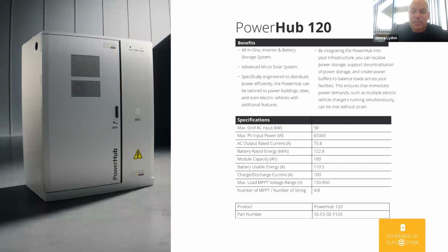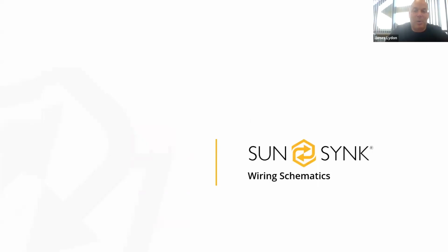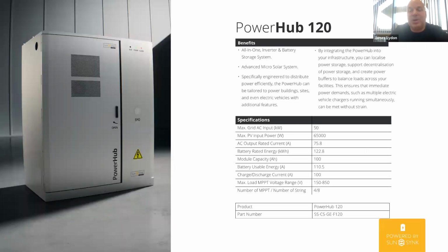The power hub, so this is obviously an outdoor unit, and this essentially has the high voltage kit built in as standard. So inside the power hub, you've got a 50 kilowatt hybrid inverter and two of our 61.4 kilowatt hour stacks. So just over 120 kilowatt hours of storage. And the power hubs are great because they're all pre-wired. You don't need to do anything. They get delivered to site, you terminate your grid feed into it. If it's been AC coupled, you're not having to mess around with a lot of wiring, essentially. We just need that grid feed and RCT on the incomer. But these are fully DC coupled and AC coupled.